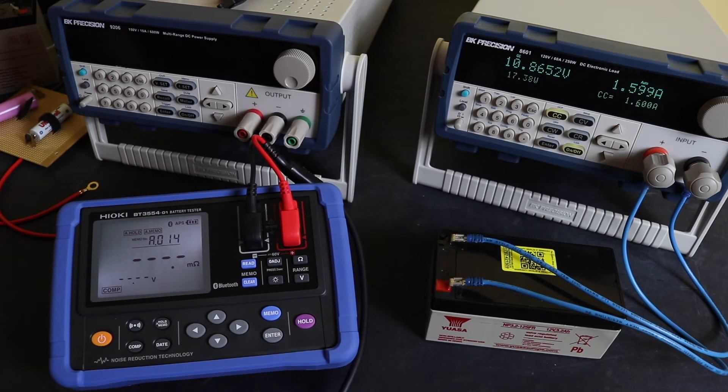And then hopefully see that it will show a fail on this instrument, because in general this test would only ever be done with the batteries on float charge. Never do an impedance test with them on discharge mode like this, because they do just end up giving you a failure reading.